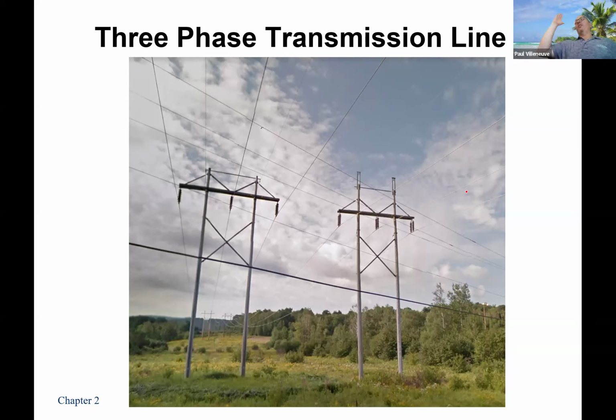Because if you think about it, all these wood poles do is keep the wire up in the air. A wire is pulling this way, but that same wire is pulling this way, so they balance each other out. So there's no force at the top of the pole other than keeping it from falling on the ground.